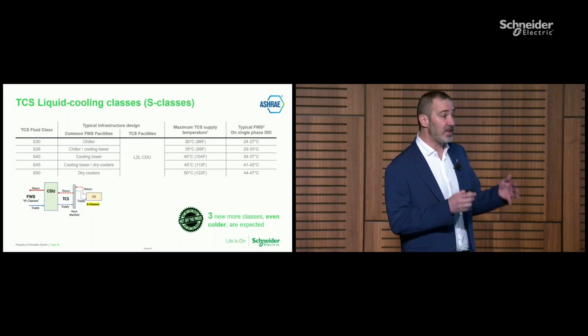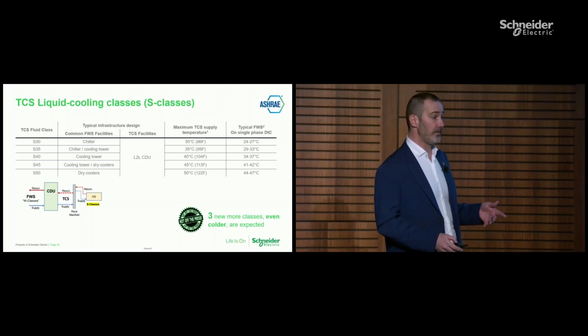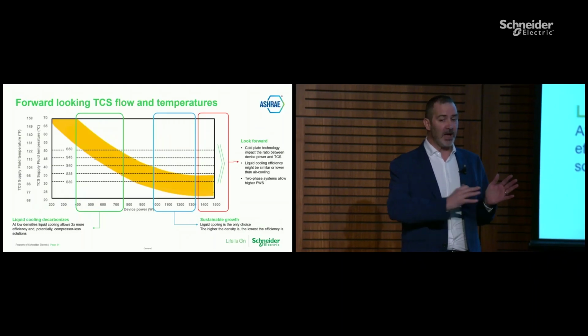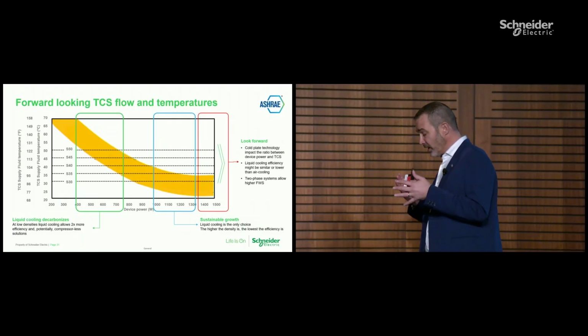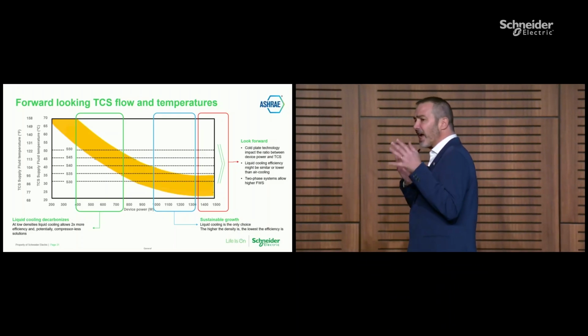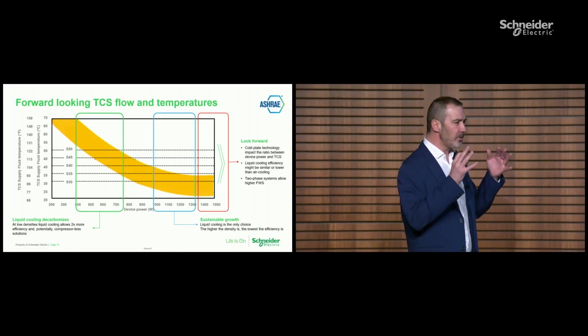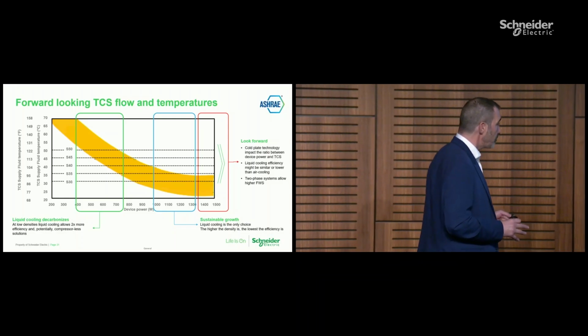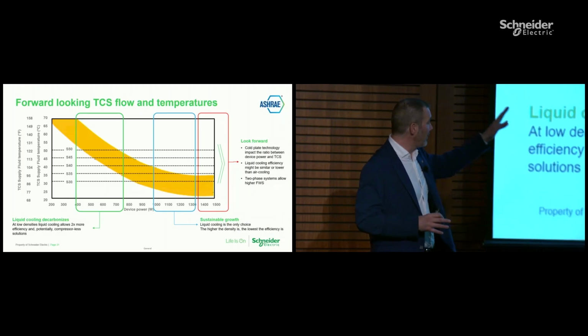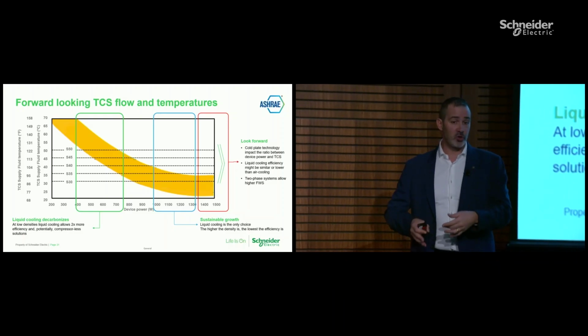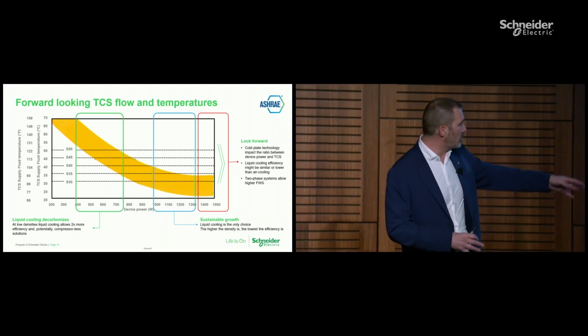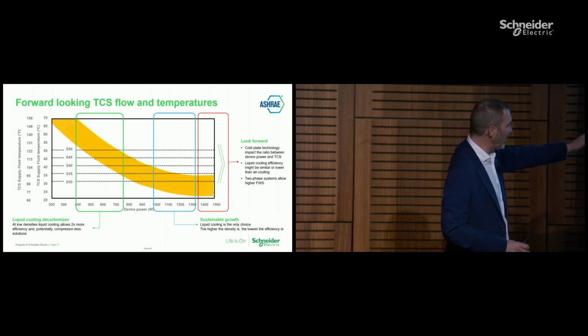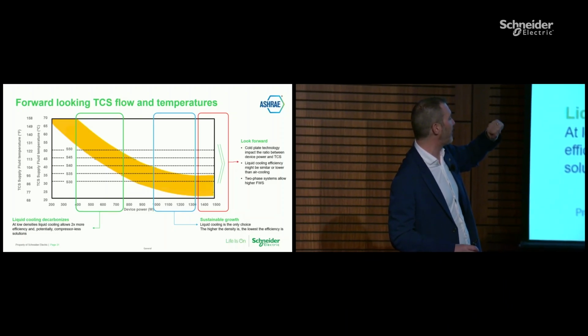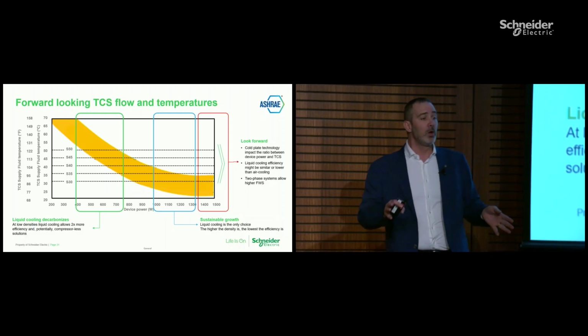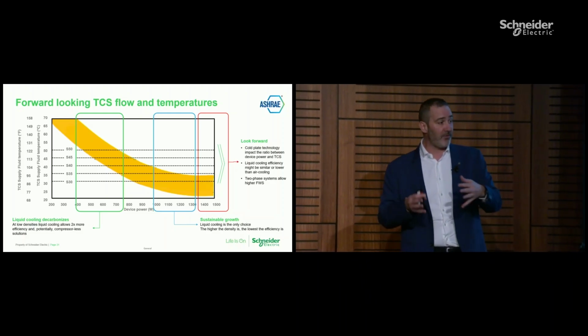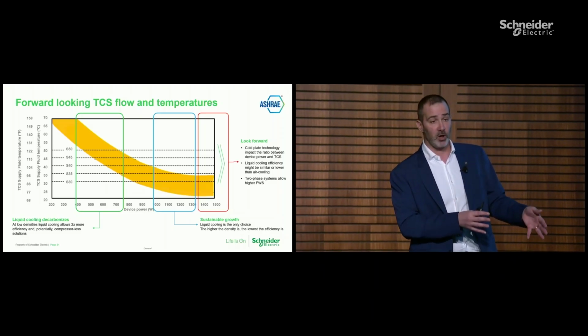The key point is that the S-class depends on the density. Looking at the density, there is a rule: the higher the density, the lower the temperature must be. This depends on the server technology, the cold plate technology. So don't consider it a golden rule that a 600 watt per chip requires S45. It's a general indication, but the final decision is on the server technology.